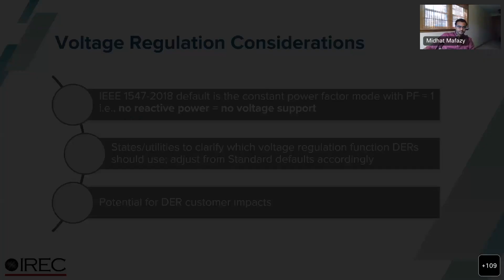As I mentioned, the 2018 version includes 90-some pages on technical requirements for DERs. What you need to know is that there is no one way to apply the standard, which makes it a little harder to adapt compared to the 2003 version. The standard provides a menu of items to select. This includes the level of ride-through, category 1, 2, or 3, reactive power capability, category A or B, and communication protocols. Similarly, the use of voltage regulation is optional. By default, voltage regulation is not activated. And depending on how voltage functions are deployed, there is potential for DER customer impacts through curtailment functions. Next slide.